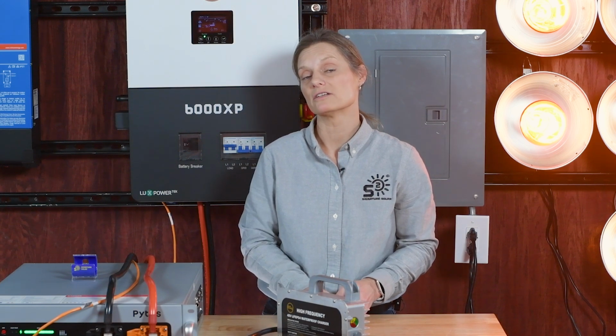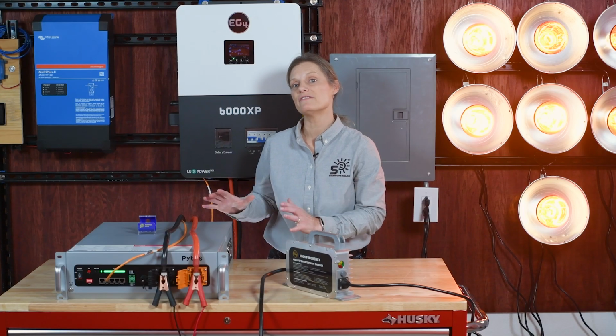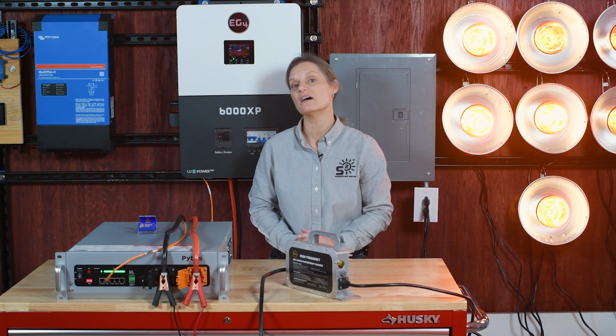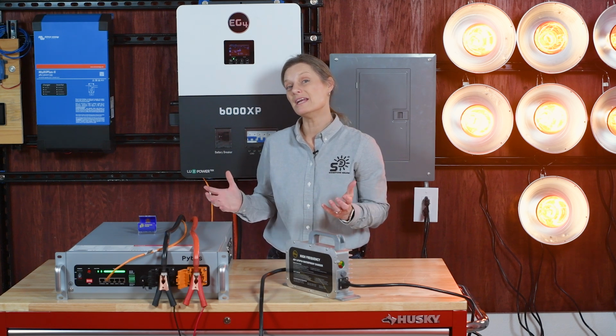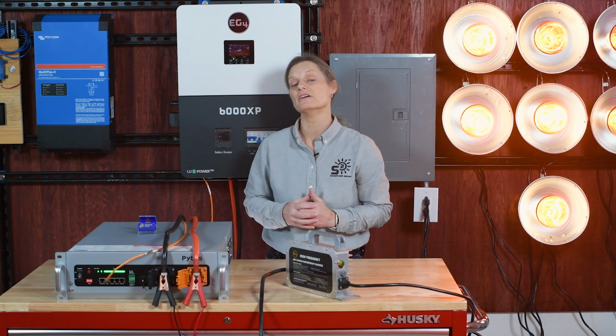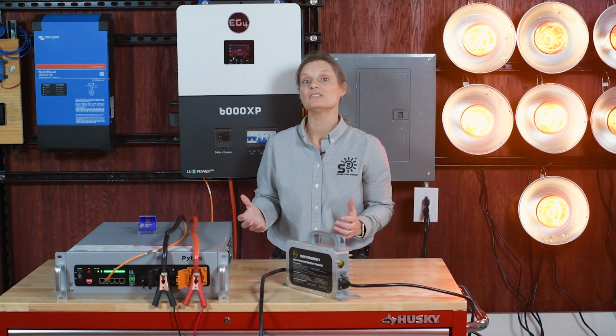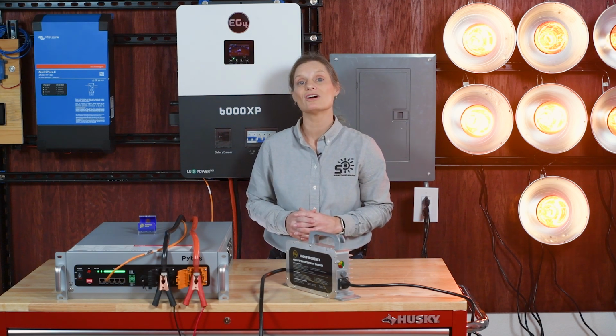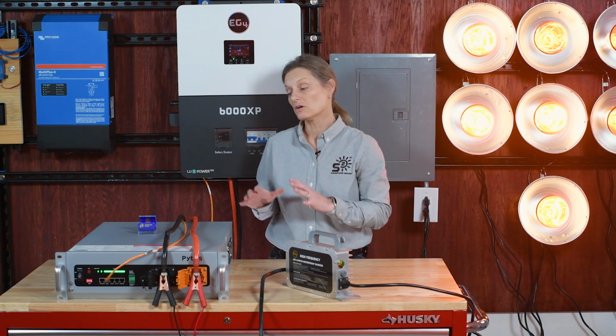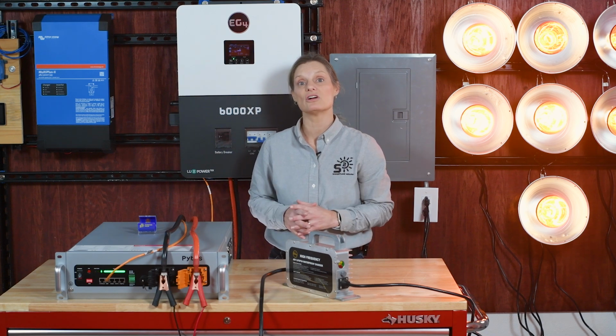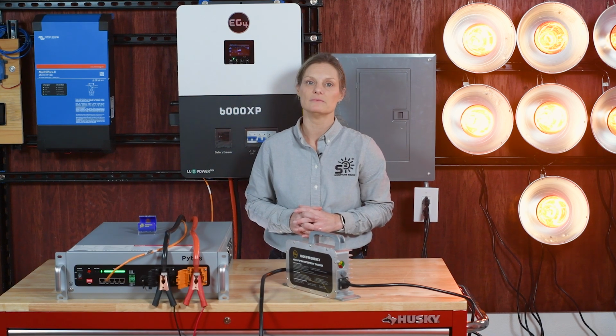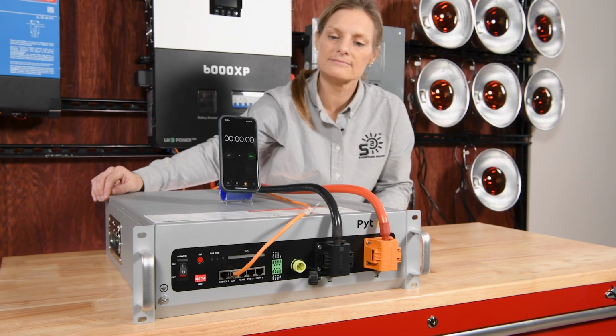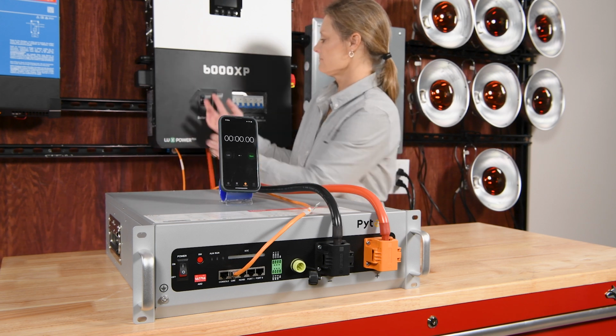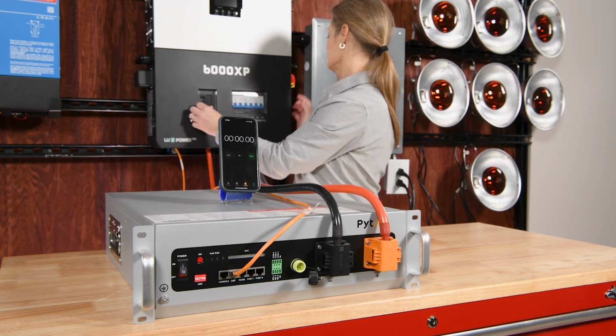However, that's a rough estimate and doesn't account for a few factors. First, Pytes state that the V5 has a round-trip efficiency of over 95%, meaning we might lose a small amount of energy in the process. Additionally, the battery's depth of discharge is set to 90%, so the BMS will stop the discharge slightly before reaching zero. With these factors, it will take slightly less than 2 hours and 45 minutes to fully discharge.